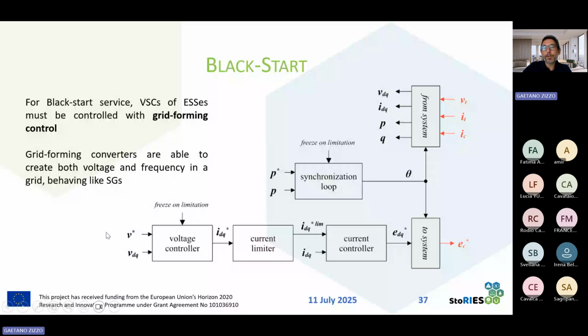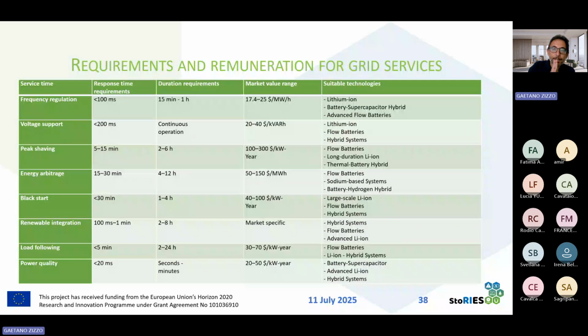This is only one of the possible implementations of grid forming, but grid forming converters are usually converters that are connected to batteries, but also to wind plants, photovoltaic systems, and can be operated like they were synchronous generators connected to the grid. So they are able to create both voltage and frequency in a grid totally shut down. For providing each service, we can use different technologies. In this figure, you see for each service which battery technology is more suitable.